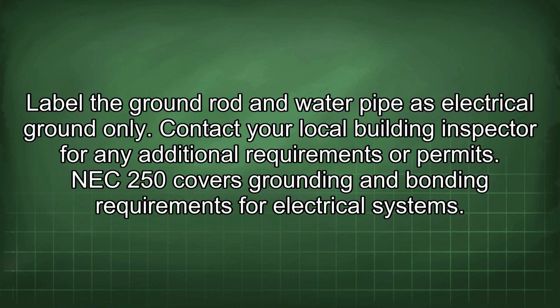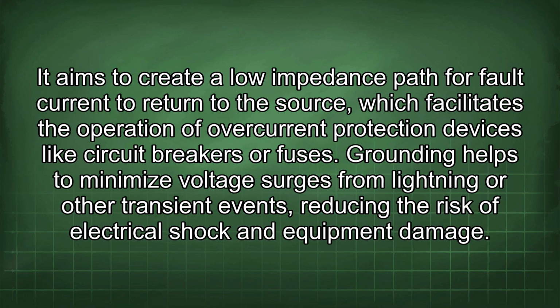NEC 250 covers grounding and bonding requirements for electrical systems. It aims to create a low impedance path for fault current to return to the source, which facilitates the operation of overcurrent protection devices like circuit breakers or fuses. Grounding helps to minimize voltage surges from lightning or other transient events, reducing the risk of electrical shock and equipment damage.